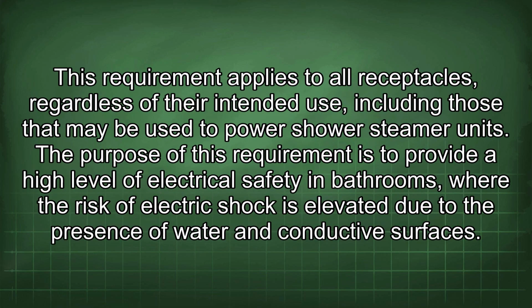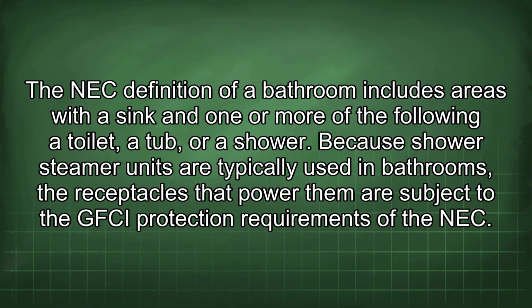This requirement applies to all receptacles, regardless of their intended use, including those that may be used to power shower steamer units. The purpose of this requirement is to provide a high level of electrical safety in bathrooms, where the risk of electric shock is elevated due to the presence of water and conductive surfaces. The NEC definition of a bathroom includes areas with a sink and one or more of the following: a toilet, a tub, or a shower.